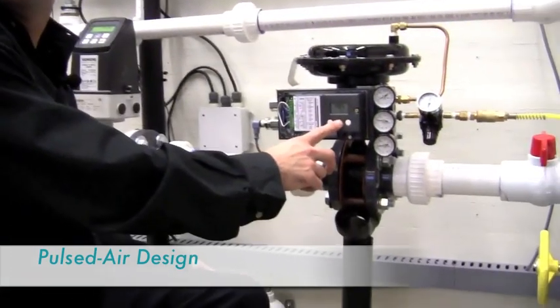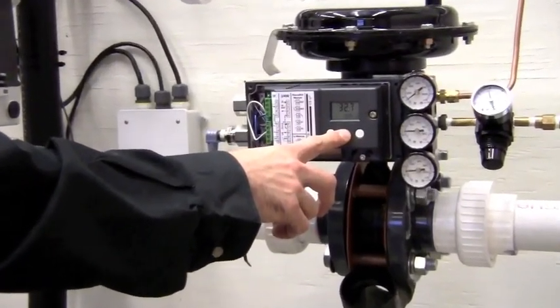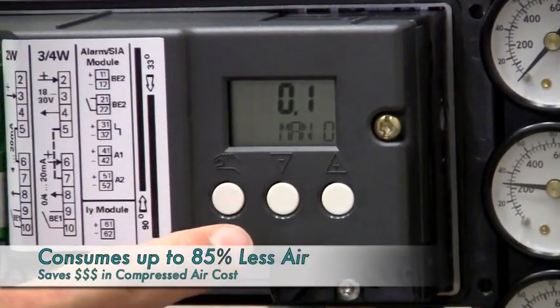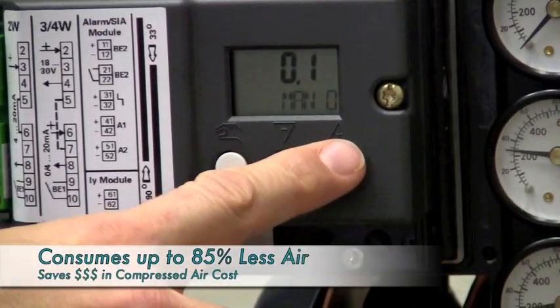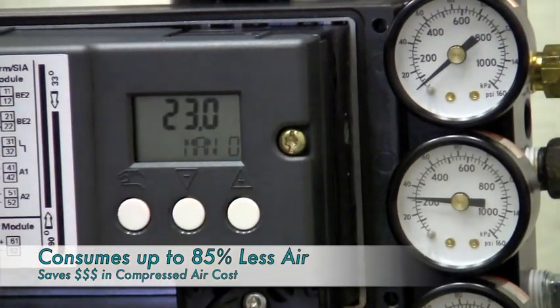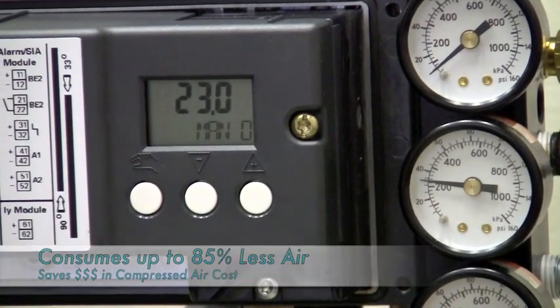The PS2 uses a unique pulsed air design to deliver air to the actuator. Unlike most other conventional positioners, which have a flow of air all the time, this means that on average the PS2 consumes 85% less air to do the same job as a conventional valve positioner.